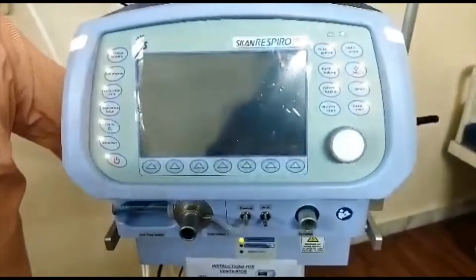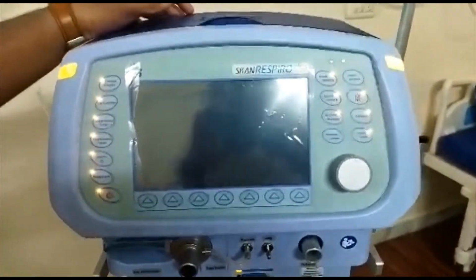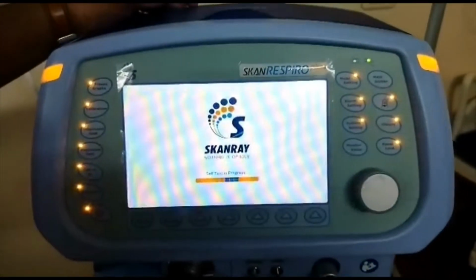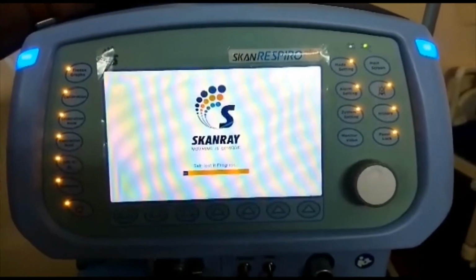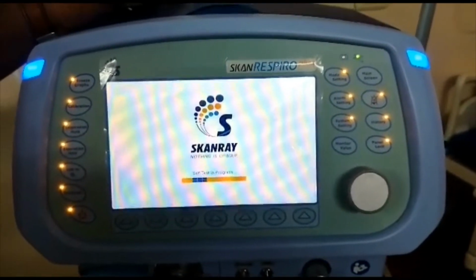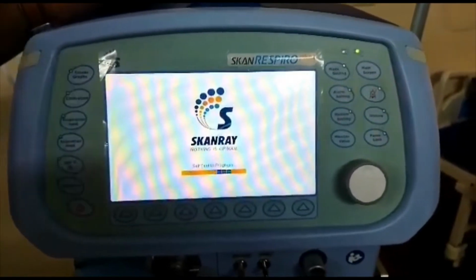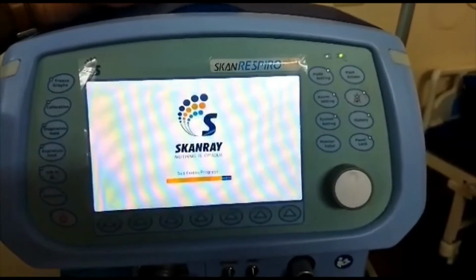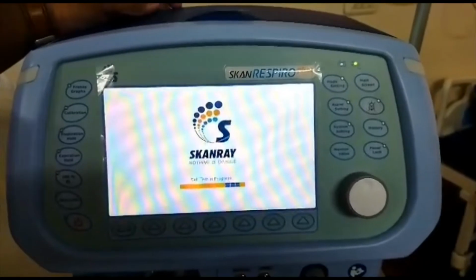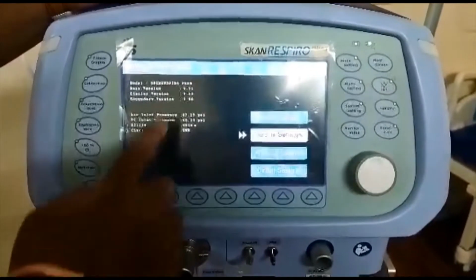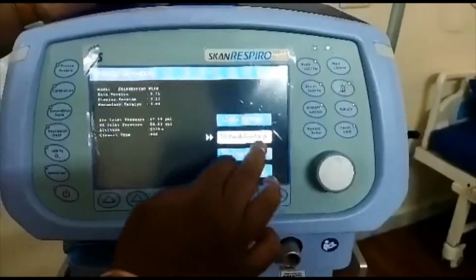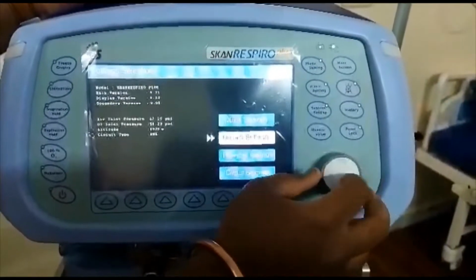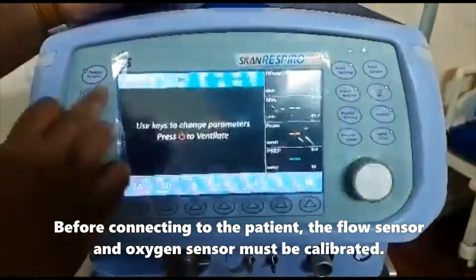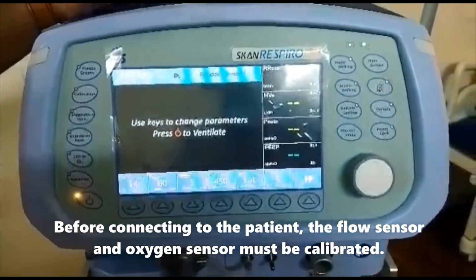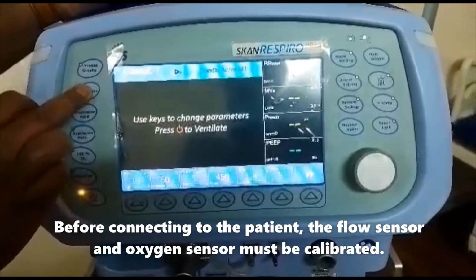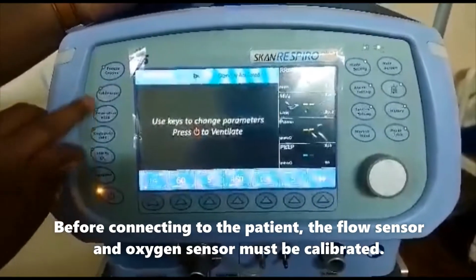So once you switch on the ventilator, the display will be starting up. The air pressure and the oxygen pressure should be more than 50 psi. So the pressure is okay. Before connecting to the patient, the flow sensor and the oxygen sensor have to be calibrated. So now the process of calibration will be going on.